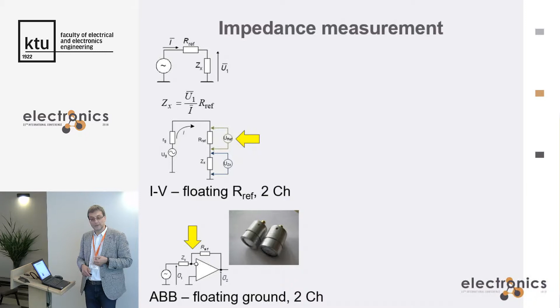We propose using this standard technique for complex impedance measurement of the ultrasonic transducer. The idea is simple: you measure the output voltage of the transducer under two load conditions—one low impedance load (RL) and one high impedance load (R). These give the equations needed, and the equation for impedance measurement turns out to be simple.